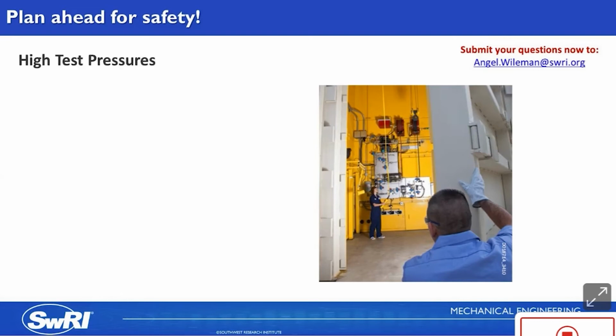The first safety consideration for fugitive emissions is the high test pressures. As I just mentioned, we've been asked to qualify up to 15,000 psi, and since gas is compressible, the amount of stored energy in the valve, especially large valves, is extremely high. So let's go over some methods we have put in place to mitigate the risk of a pressure-related safety incident.